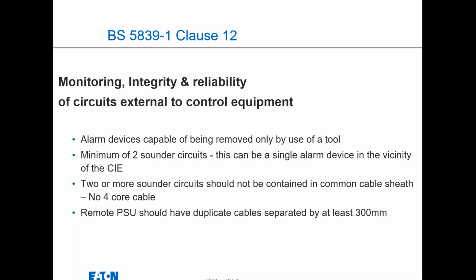So again, a minimum of 2 sounder circuits from a system, single alarms in the vicinity of the control indicating equipment, and 2 or more sounder circuits should not be contained within the same common cable sheath or tray. So you should try and do some diverse routes. Again, that sometimes falls under different standards, where you've got the electrical regulations, whatever edition they're on now, 18th edition, 19th edition.